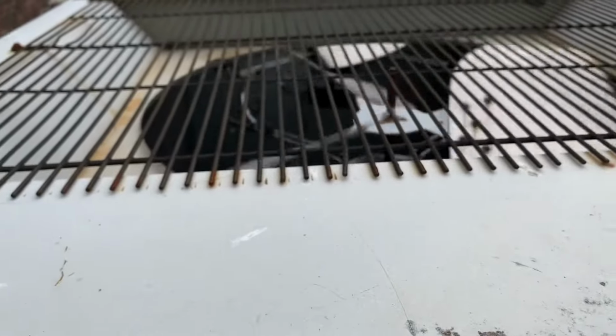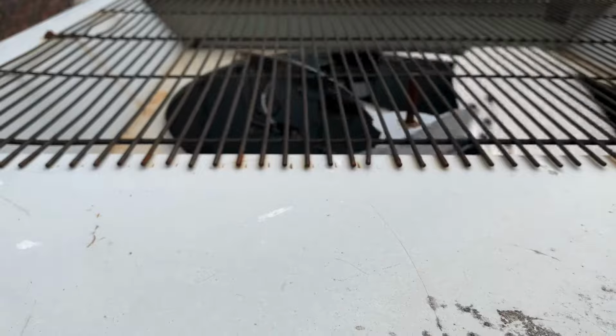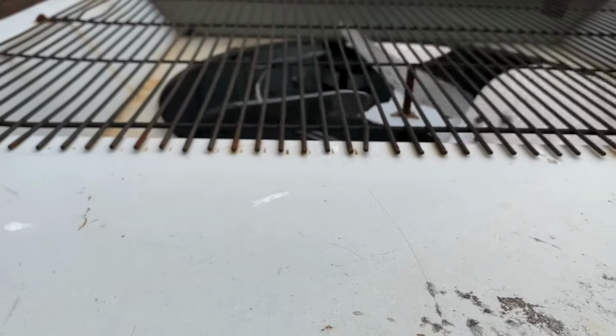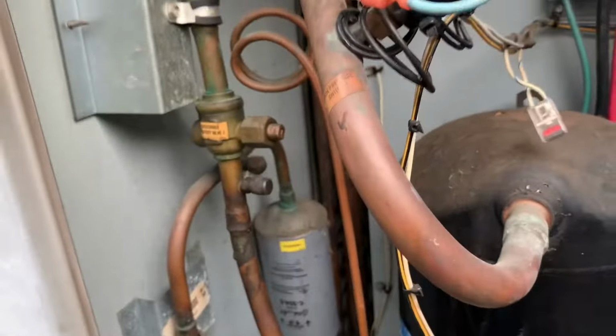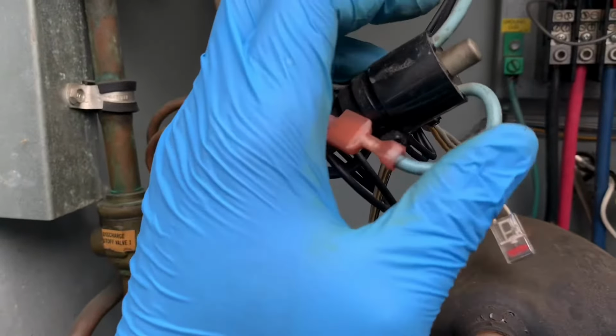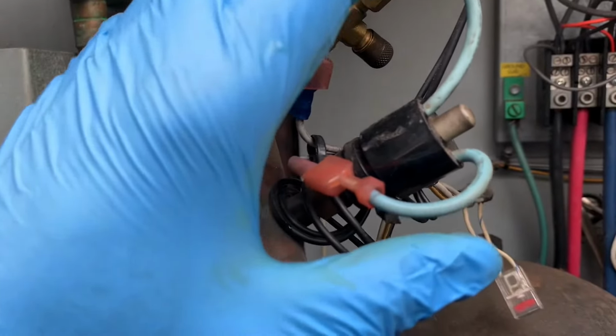So if the operating pressure goes above normal, the switch will trip, right? I'm going to rise up a little bit so we can have less noise. So if the operating pressure goes above normal, the switch will trip, protecting the compressor. And when that happens, you have to press that button on the top to reset and resume operation of your cooling or your compressor. So that's the high pressure switch for you right here, and this particular one has the manual reset. They don't all come with manual reset.